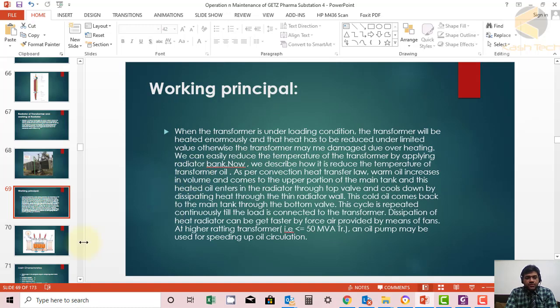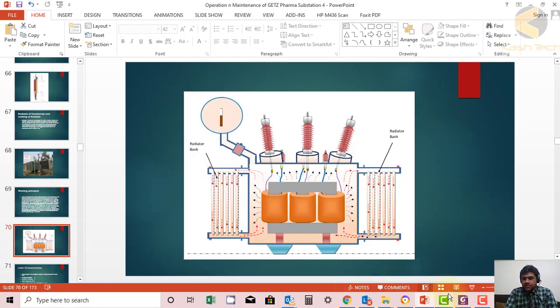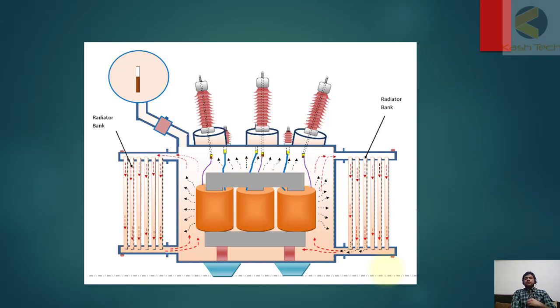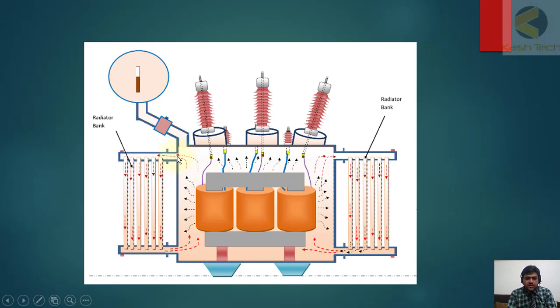Let's move to the next slide to show how these are really operating. In this picture you can see how the radiators are working. Current is flowing through the winding, which produces heating. The oil heats up, and this heated oil rises and through this pipe it goes to the radiators.